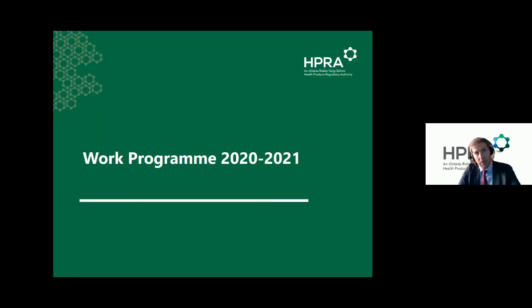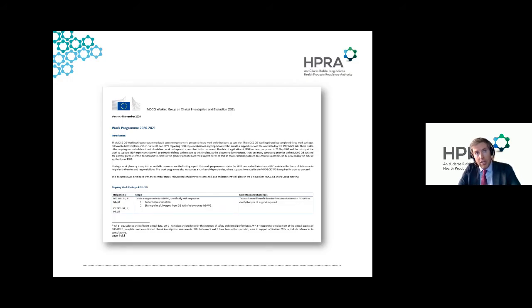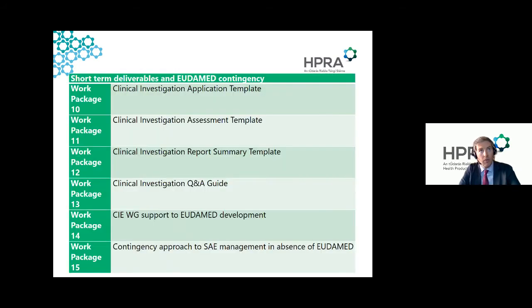Moving on to our work program — this is what we endorsed last week at CIE — the eight work packages. As chairs, Tom and Paul have been planning since summer for the different work packages, taking suggestions from all member states, then discussing, prioritizing, and agreeing the program. Work packages 10 to 15 are called short-term deliverables or EUDAMED contingencies — system needs to address before next May, often with expedited timelines. Work package 10 looks at clinical investigation application templates. We have prepared templates for the EUDAMED development team but will need standalone templates, possibly as a PDF with integrated XML to support standard data fields.